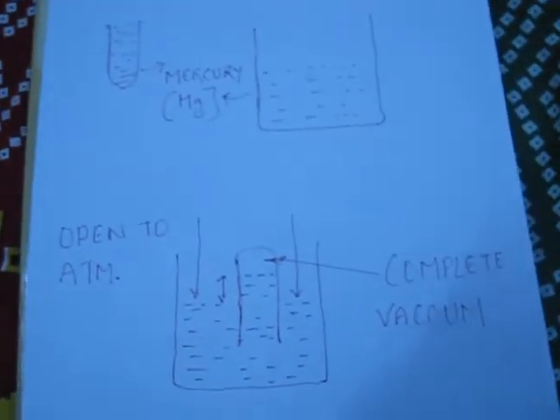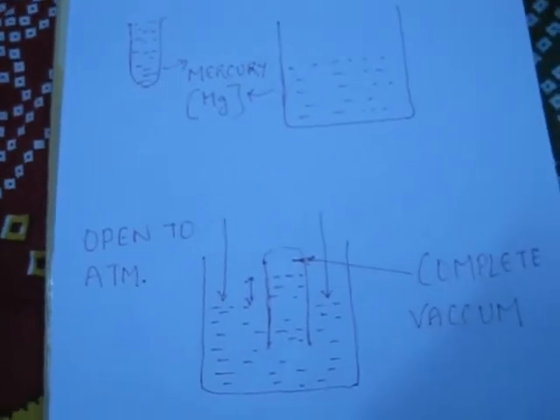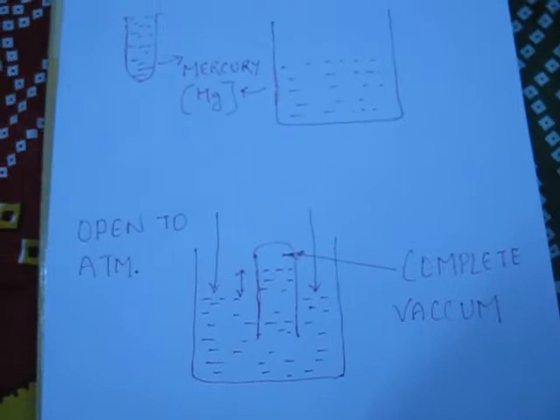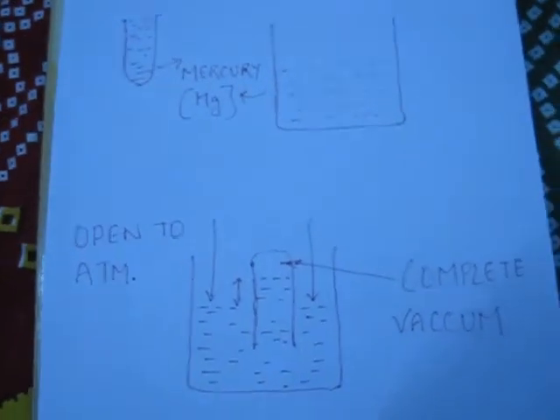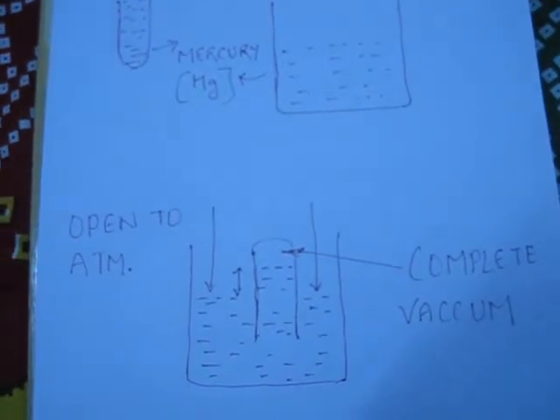So that is the reason that you cannot suck water not only below 10 meters. If the depth is 10 meter, you cannot even suck it out. Even if it is 6 meter or 7 meters for centrifugal pump.